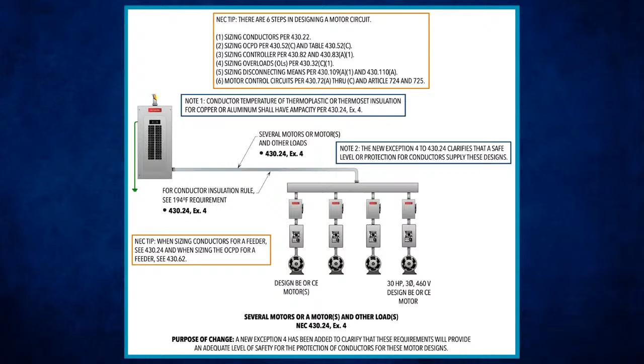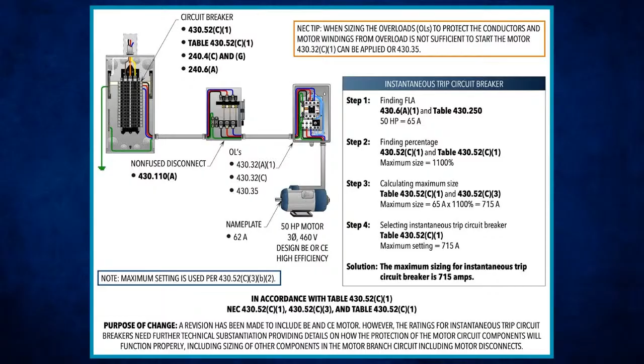Now, what they did here is a little revision, also including BE and CE motors, where you're doing an instantaneous trip breaker, and it's the same type of calculation. We got 50 horsepower at 65 amps, the maximum size was 1100%, so your maximum setting for this instantaneous trip circuit breaker would be 715 amps. Same type of calculation. We took the time to draw these out so it's easier to understand exactly what they did.